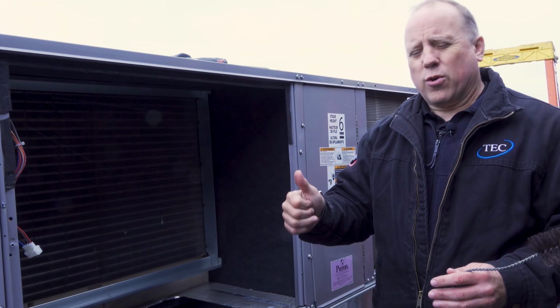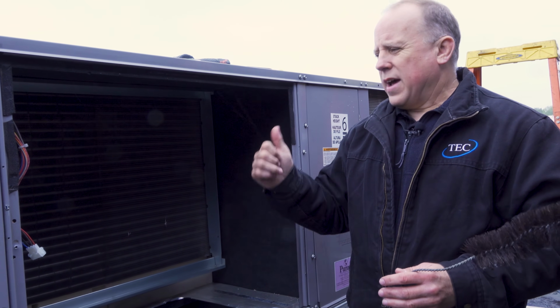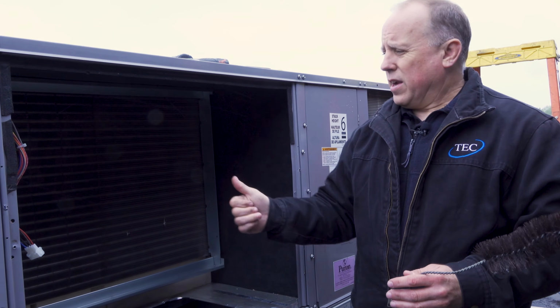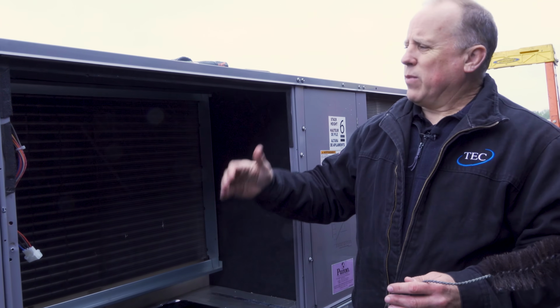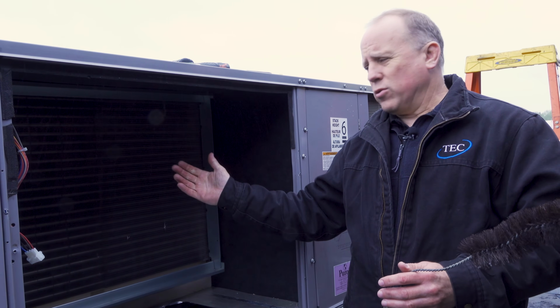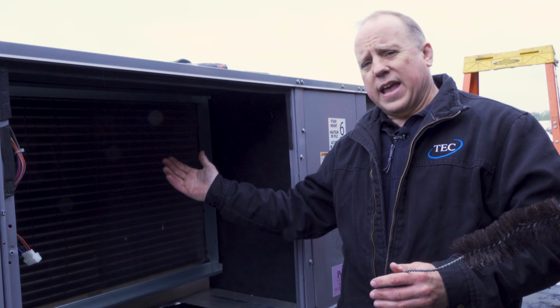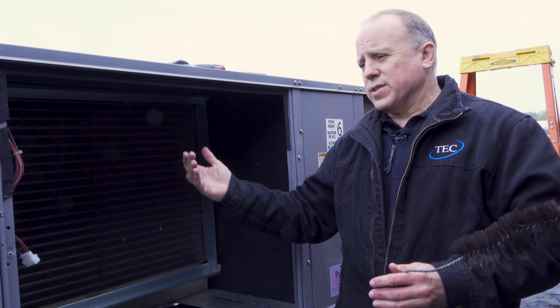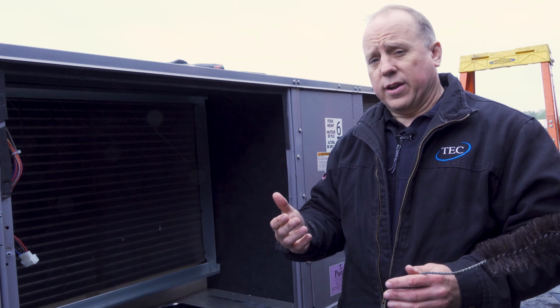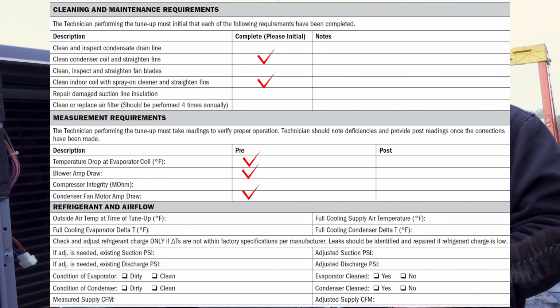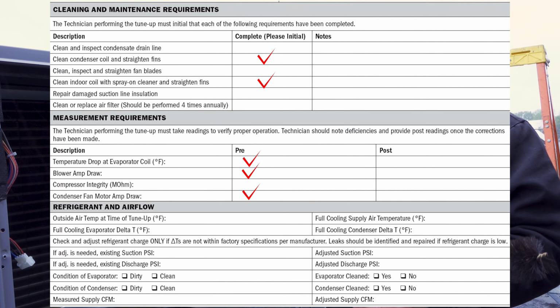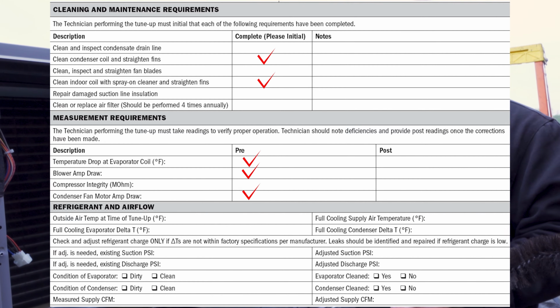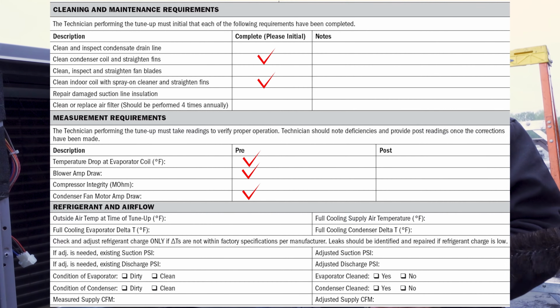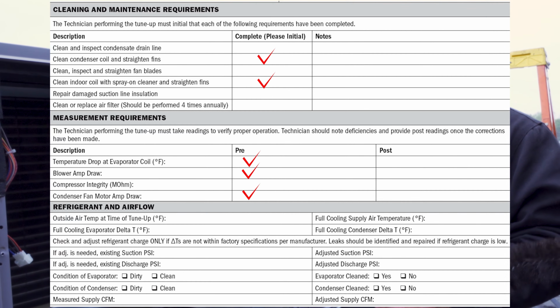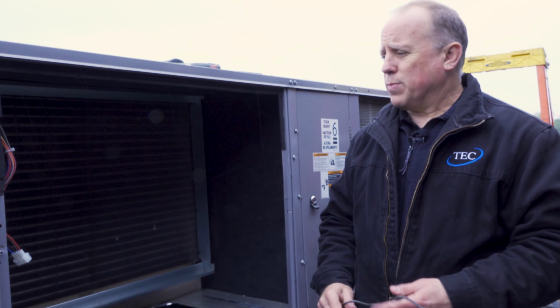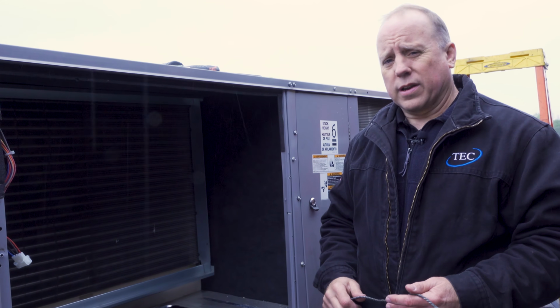Depending on how bad the coil is, what type of cleaner you're going to use and how you're going to go about cleaning it, is it going to need to be rinsed or not? And then again, we could go to the other side of that coil depending on how dirty it is, and clean from that side also, possibly using a foaming cleaner if it's really bad and you have to use it. The thing you have to worry about with certain cleaners, though, are the odors and fumes they might give off. It might be a problem if there are people in the building, and there may be issues there. So always be aware of the type of cleaner you're using when you are cleaning coils.